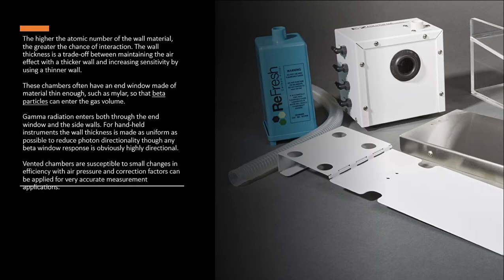For handheld instruments, the wall thickness is made as uniform as possible to reduce photon directionality, though any beta window response is obviously highly directional. Vented chambers are susceptible to small changes in efficiency with air pressure, and correction factors can be applied for very accurate measurement applications.